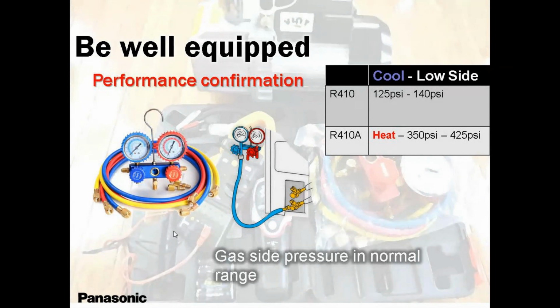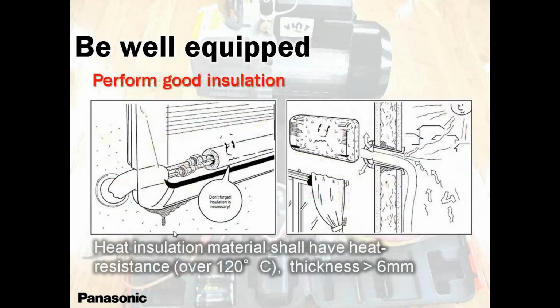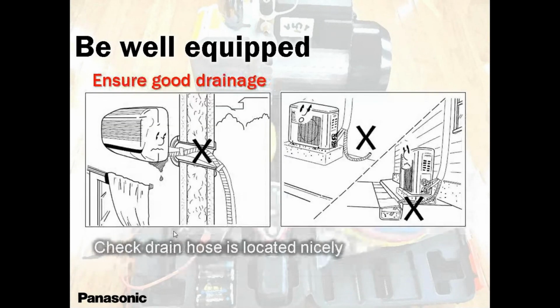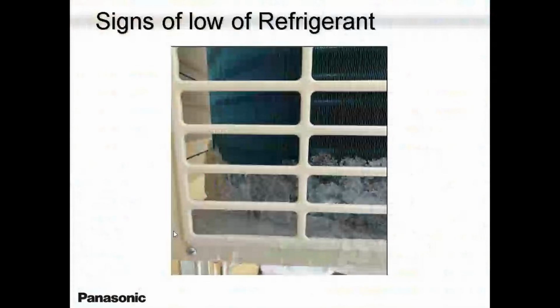Again, run the system, check the performance, check the intake and the exhaust, discharge and intake. You know, cooling 8 degrees. If it plays around 7, 8, 9, it's okay. And 12, 13, 14 is okay. But in that range, not a huge delta T, you know. If you have a huge delta T, then we have a problem.